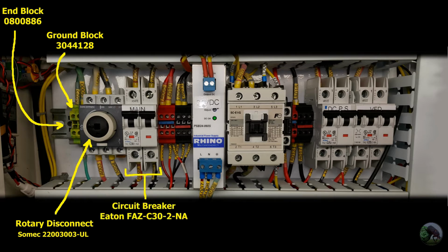So next up is the main circuit breaker. So this is a two-pole circuit breaker. The two poles are bound together, so if one side pops, the other one does as well. And this is an Eaton, and it's a 30 amp and has a C tripping curve. So basically there's B, C, and D, which are the most common tripping curves, and C is just a little more permissive. It's meant for inductive loads, like starting large motors that might have a large current draw on startup and things like that.